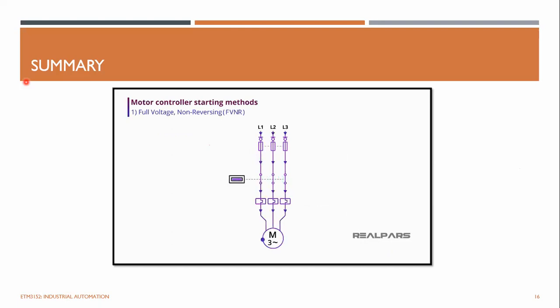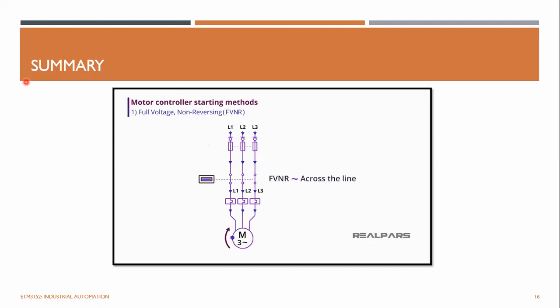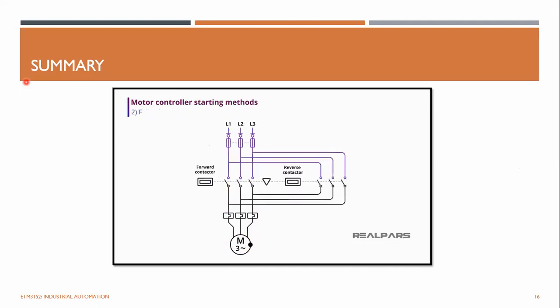With an FVNR motor controller, the position of the line phases is fixed, and the motor can only be operated in one rotational direction. An FVNR can be thought of as an across-the-line controller. In a full voltage reversing motor controller, the controller has two separate actuating states, one to operate the motor in the forward direction and one state to allow the motor to operate in the reverse direction.